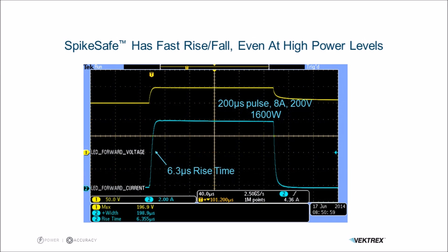The final example is a 1600 watt pulse. This one has a slower rise time of 6 microseconds, but at a 200 microsecond pulse width it still provides only a 1% error with this type of LED.